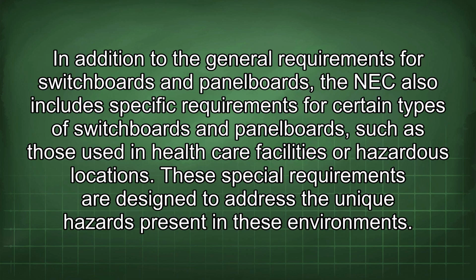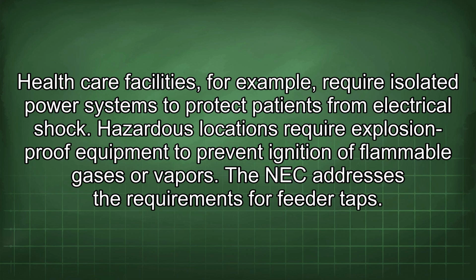In addition to the general requirements for switchboards and panelboards, the NEC also includes specific requirements for certain types of switchboards and panelboards, such as those used in healthcare facilities or hazardous locations. These special requirements are designed to address the unique hazards present in these environments. Healthcare facilities, for example, require isolated power systems to protect patients from electrical shock. Hazardous locations require explosion-proof equipment to prevent ignition of flammable gases or vapors.